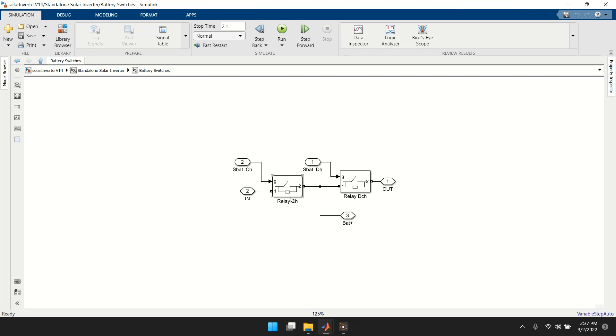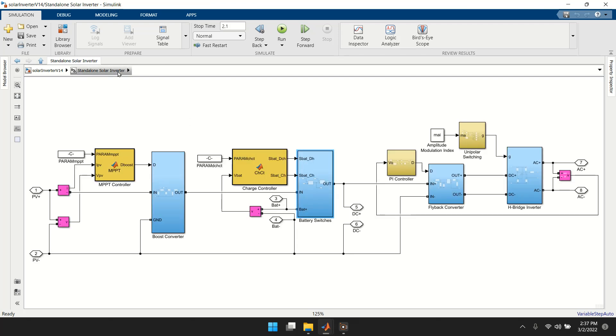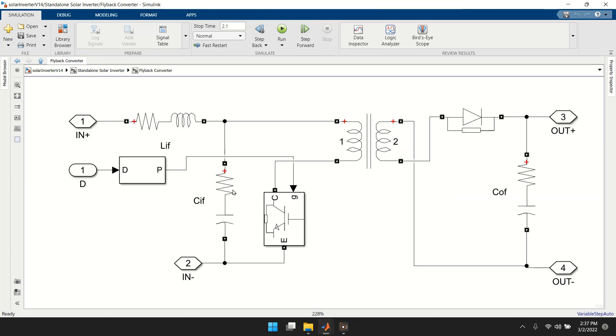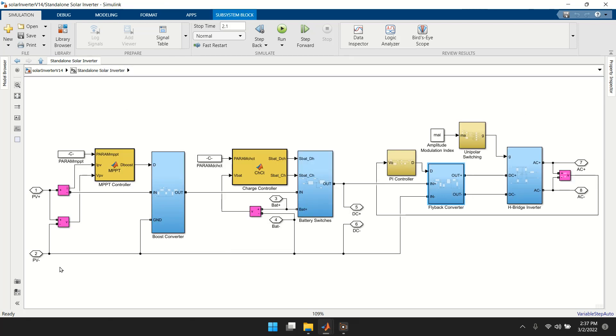The battery switches are basically a relay system for charging and discharging. Then you have a flyback converter to increase the voltage — from the battery voltage, which is quite low, up to around 320–350 VDC. After increasing the voltage, it goes to the H-bridge to be converted to AC.